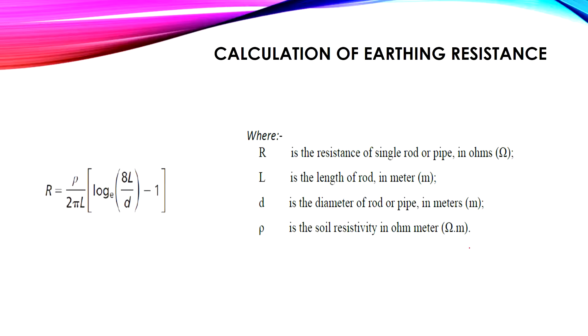The question is how to calculate the resistance of an earthing rod. The resistance of one rod is given by: R = ρ / (2πl) × (log(8l/d) − 1), where ρ is the soil resistivity, l is the length of the rod in meters, and d is the diameter of the rod. As soil resistivity increases, the resistance of the electrode increases — that is why you should have low soil resistivity during grounding.